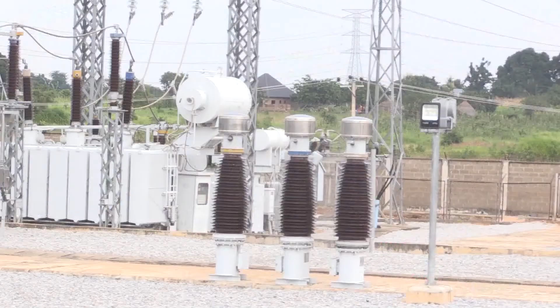The problem of over voltage will be a thing of the past, because we will be able to control the voltage at will. If the voltage becomes too low, we put off the reactor. But when it becomes too high, we bring in the reactor. It is usually for voltage control.